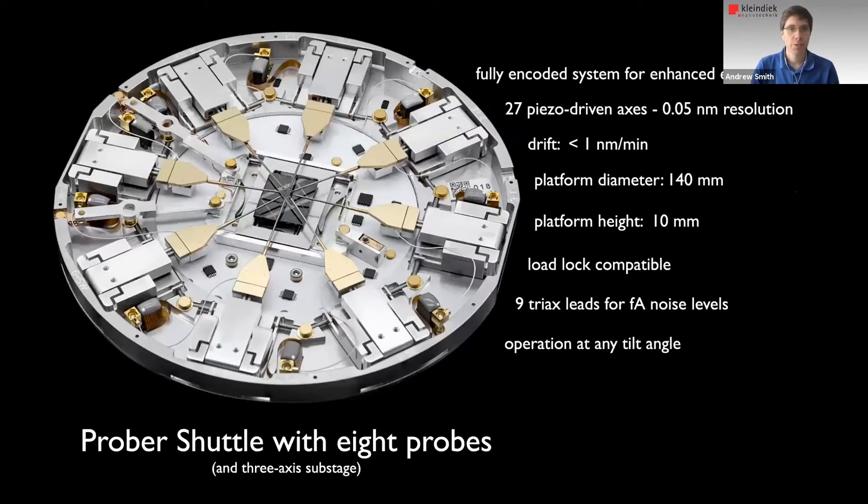The tool that I'd like to introduce for this is what we call a Prober Shuttle. The latest generation is fully encoded. It has 27 piezo-driven axes with 0.05 nanometer step size. We specify a drift of less than one nanometer per minute. The platforms I mentioned are such that it can fit through many load lock systems, so you can introduce the whole platform as well as a sample into the microscope chamber via the load lock. You don't have to vent the main chamber, and this goes in the vein of keeping things clean. We use triax leads, of course, so we get very low noise levels and we can operate at tilt angles.